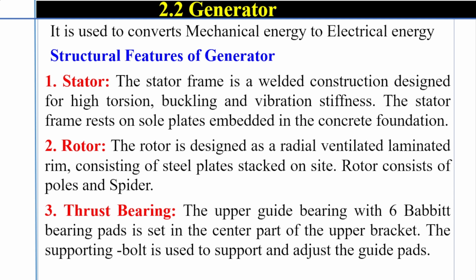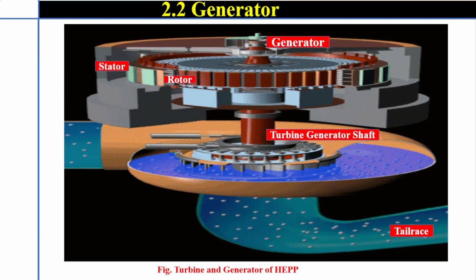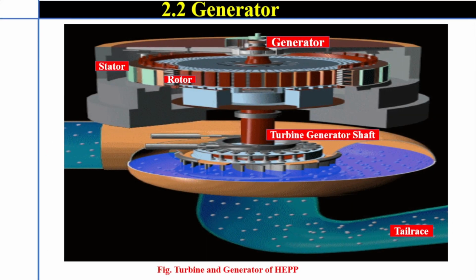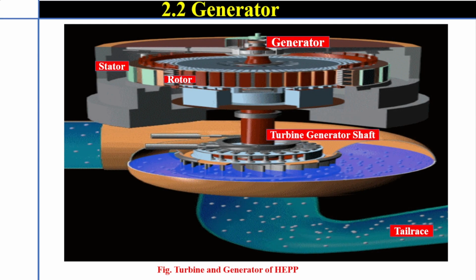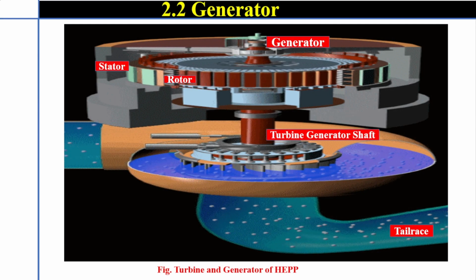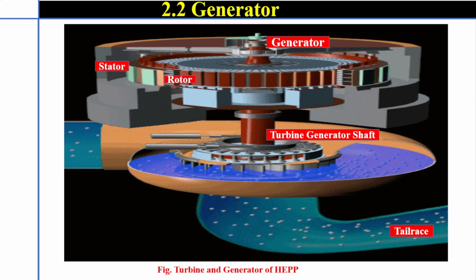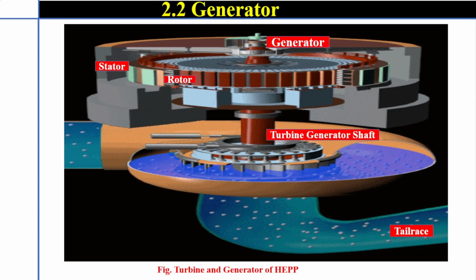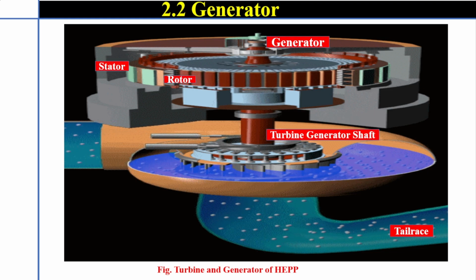Rotor. The rotor is designed as a radial ventilated laminated rim consisting of steel plates stacked on site. Rotor consists of poles and a spider. Thrust bearing. As you can see, this is the figure of turbine and generator of hydroelectric power plant. As you can see, there's rotor, stator, generator, turbine, generator shaft, and a tailrace.